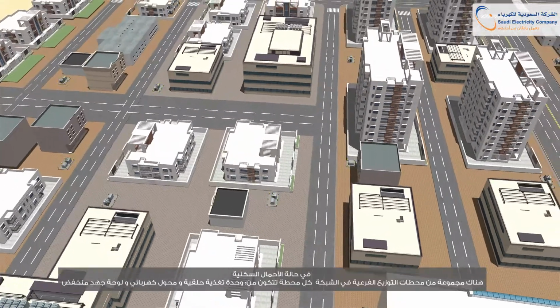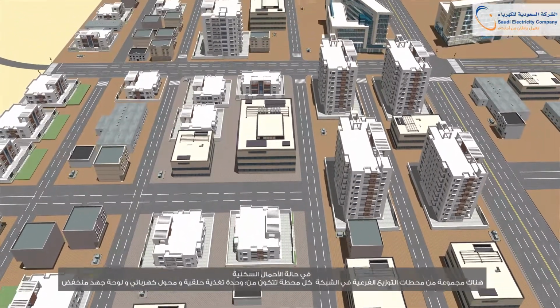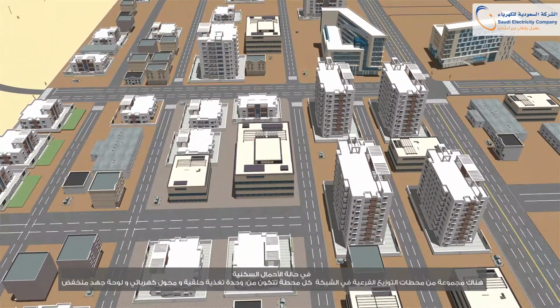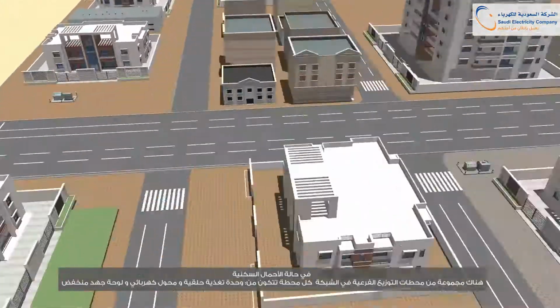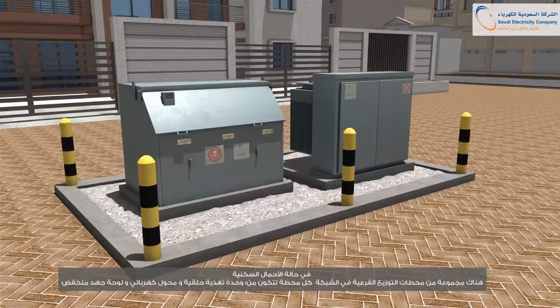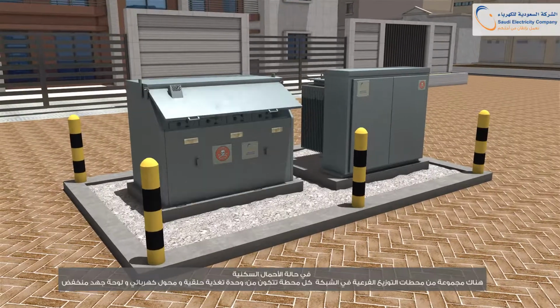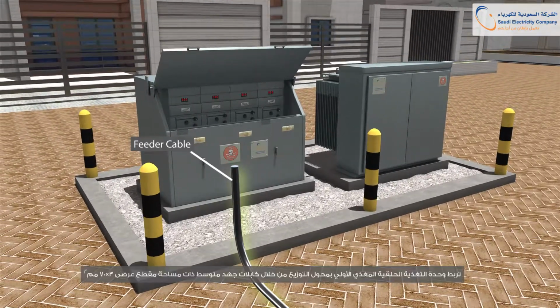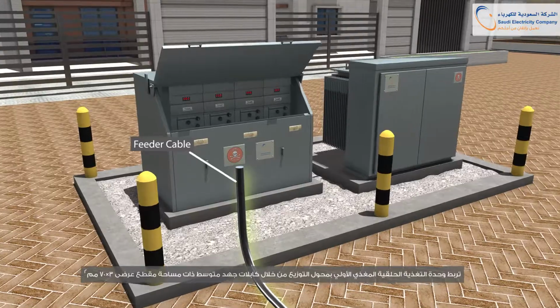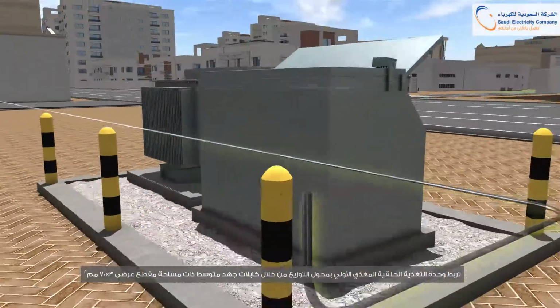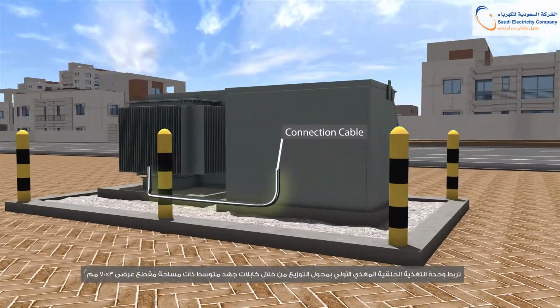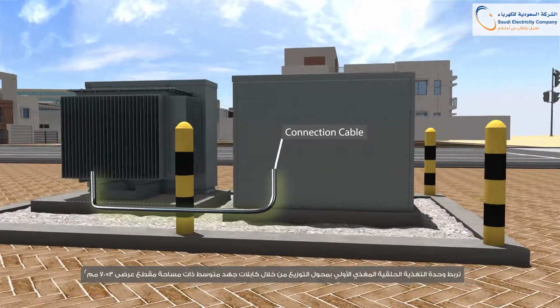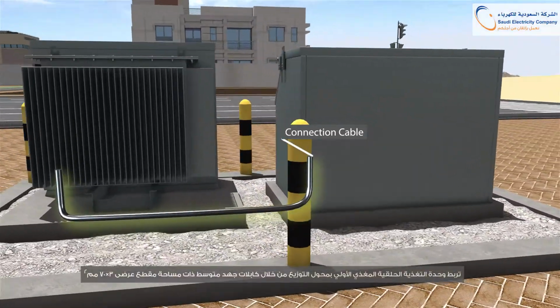In the case of the residential load, there is a group of distribution substations in the network. Each of them consists of a ring main unit, a distribution transformer, and a low voltage panel. The ring main unit connects the primary feeder with the distribution transformer through MV cables, which have a cross-section area 3 by 70 square millimeter.